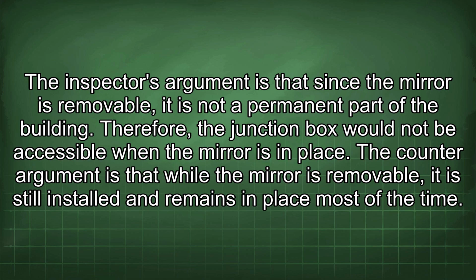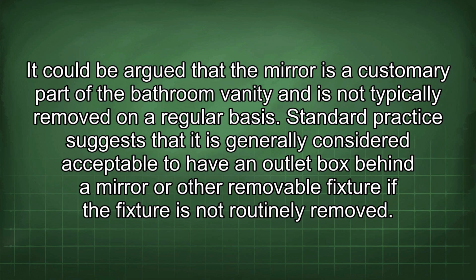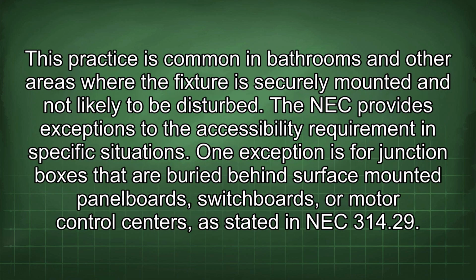The counter-argument is that while the mirror is removable, it is still installed and remains in place most of the time. It could be argued that the mirror is a customary part of the bathroom vanity and is not typically removed on a regular basis. Standard practice suggests that it is generally considered acceptable to have an outlet box behind a mirror or other removable fixture if the fixture is not routinely removed. This practice is common in bathrooms and other areas where the fixture is securely mounted and not likely to be disturbed. The NEC provides exceptions to the accessibility requirement in specific situations.